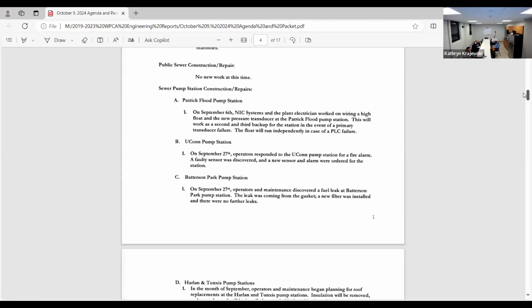And then we have a float as a third backup, which will run independently in case of a PLC failure. So there's a primary pressure transducer, secondary pressure transducer, the float, and then the float will also run on a high and a low in case the PLC failed.